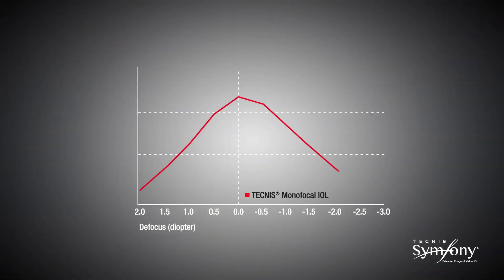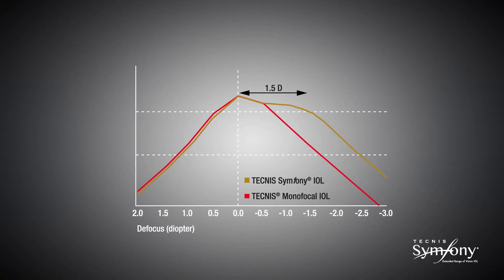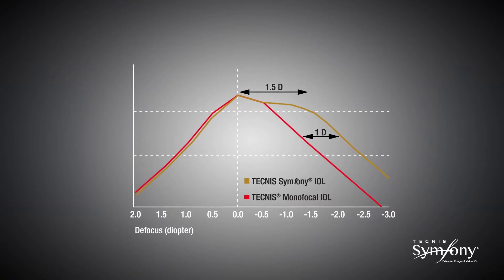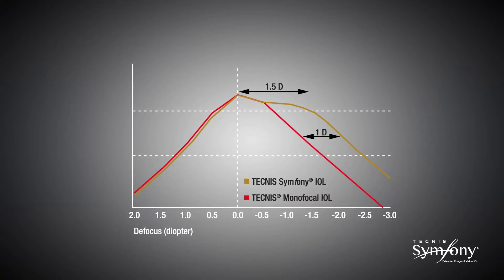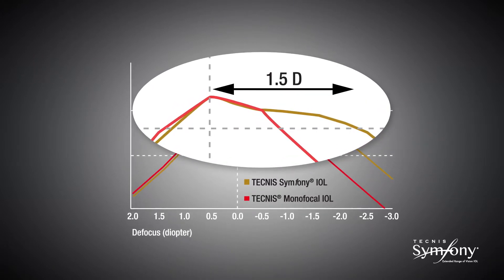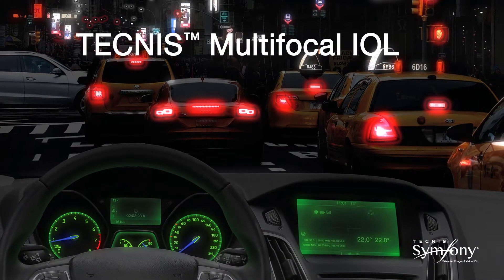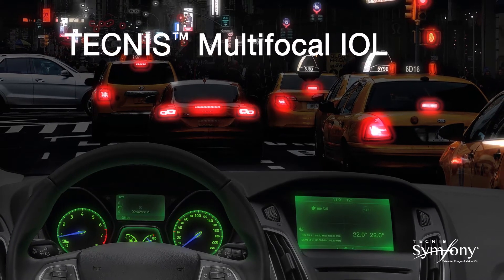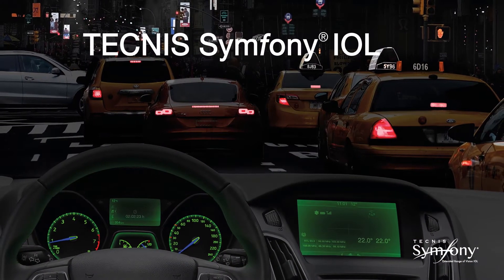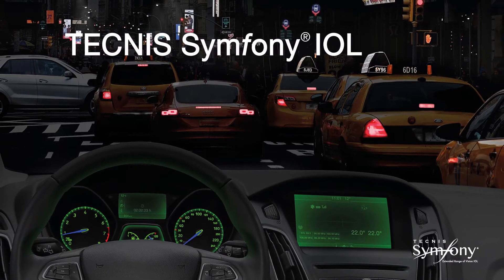Because of its elongated focus, the TECNIS Symphony IOL delivers high quality vision through 1.5 diopters of defocus and an increase of 1 diopter range of vision throughout the defocus curve compared to a monofocal IOL. The plateau of the defocus curve demonstrates the extended range of vision of the TECNIS Symphony lens. In addition, because of the elongated focus, the TECNIS Symphony IOL does not have the distinct focal points of a multifocal IOL, and as such does not have the distinct out-of-focus images that can lead to halo and glare. As a result, the incidence of nighttime halos and glare is low.